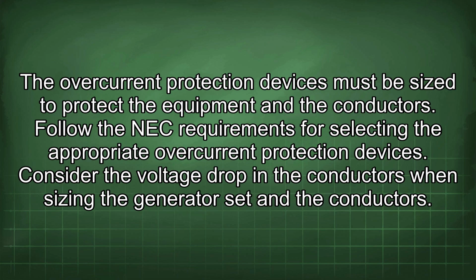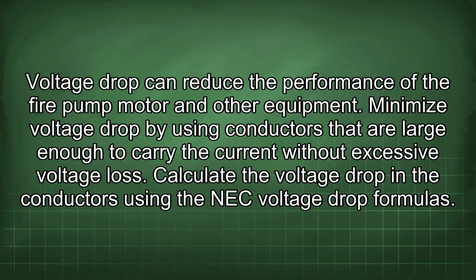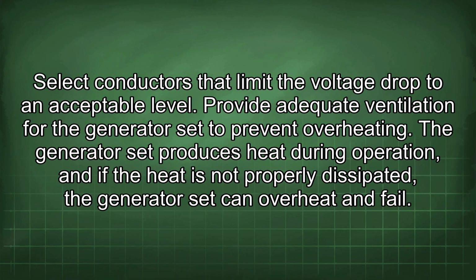Consider the voltage drop in the conductors when sizing the generator set and the conductors. Voltage drop can reduce the performance of the fire pump motor and other equipment. Minimize voltage drop by using conductors that are large enough to carry the current without excessive voltage loss. Calculate the voltage drop in the conductors using the NEC voltage drop formulas. Select conductors that limit the voltage drop to an acceptable level.